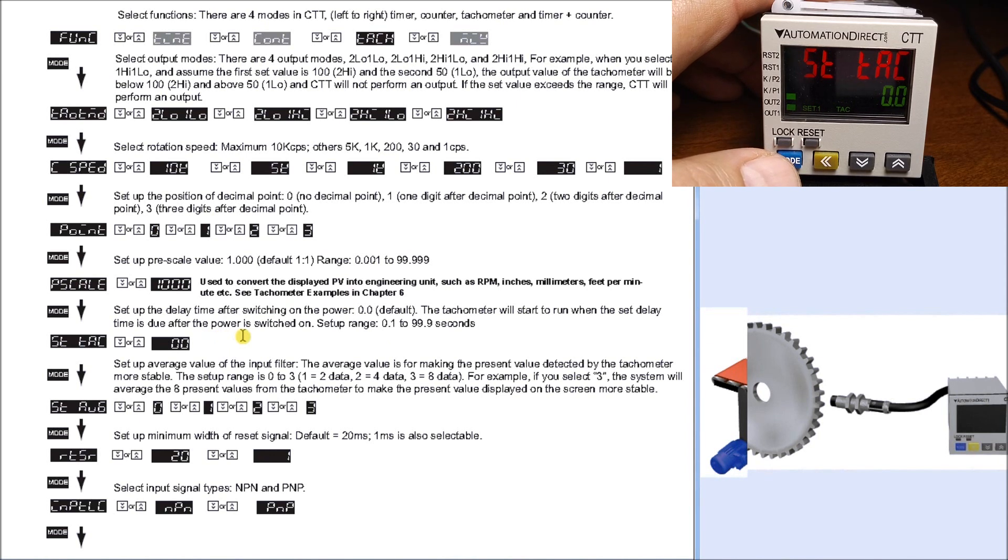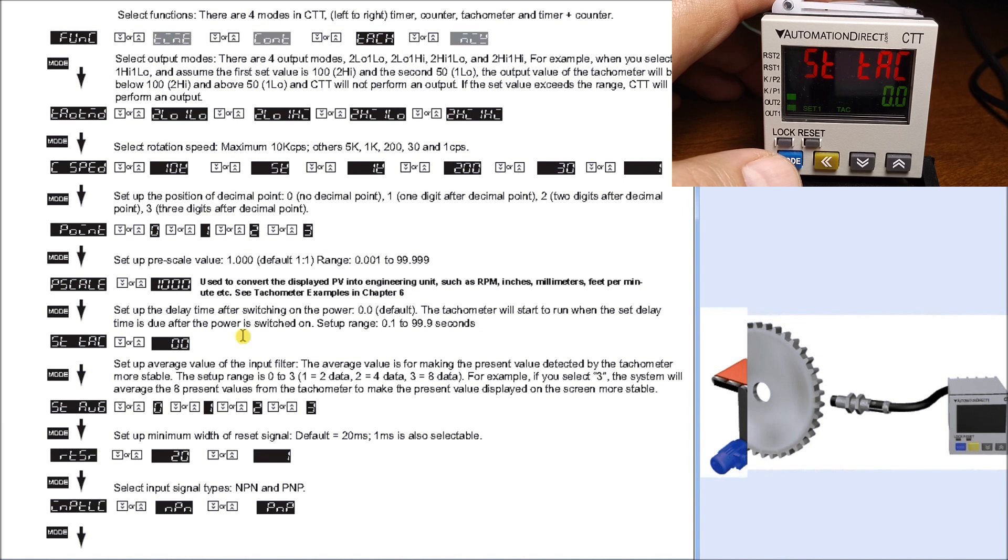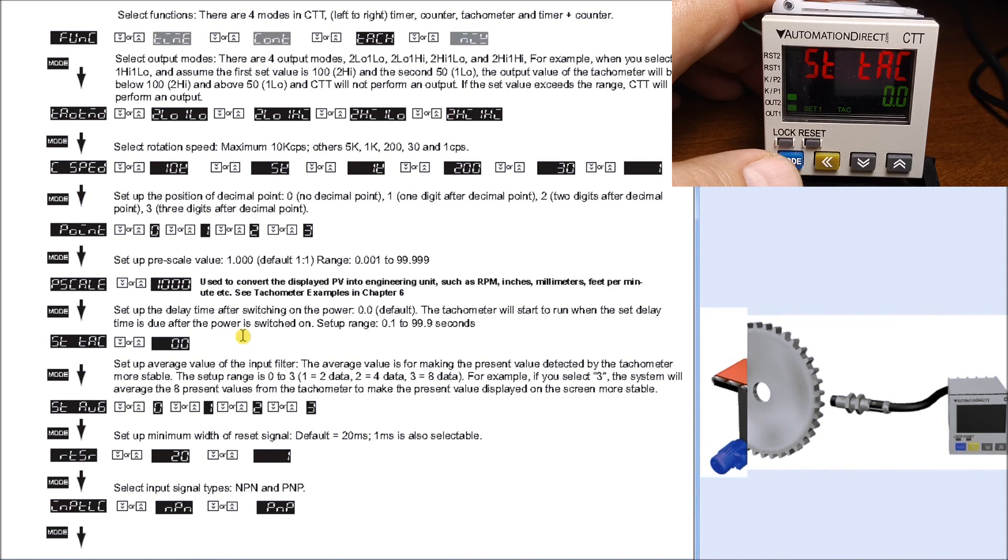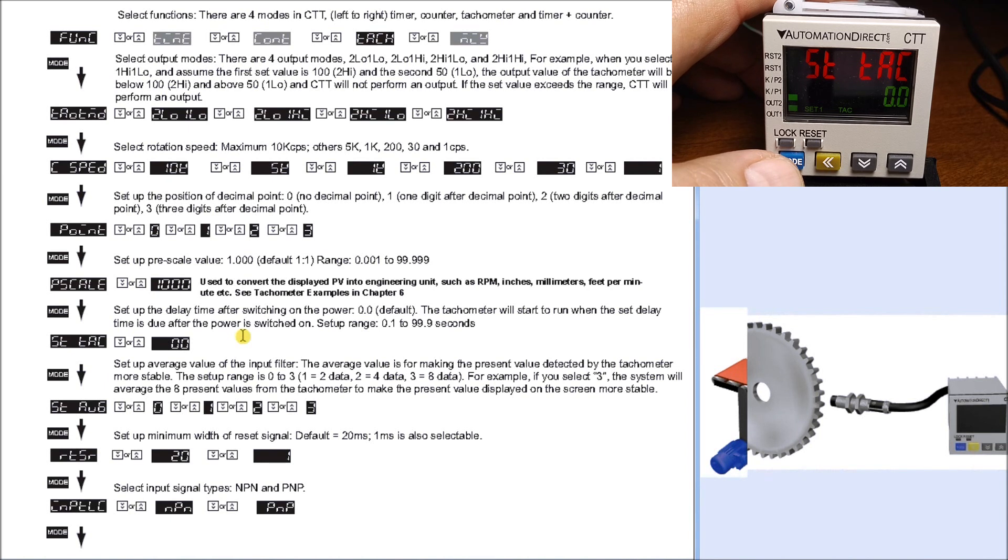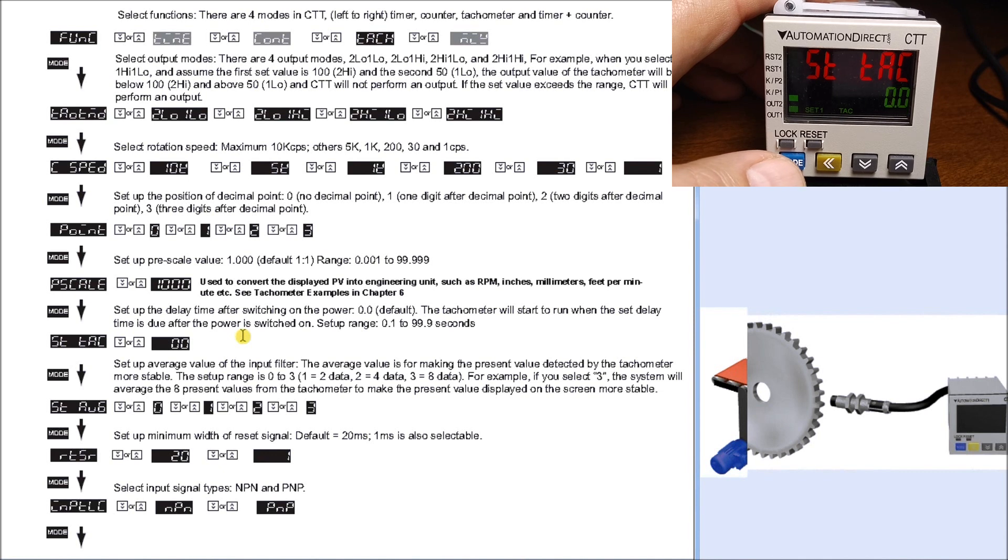Hit mode again, this mode sets up a time delay after we switch power onto the unit. Our default is set for zero, but we can set anywhere from 0.1 to 99.9 seconds. This means do not activate your output relays until you sample that pulse train coming in and determine what happens. That's a very nice feature.